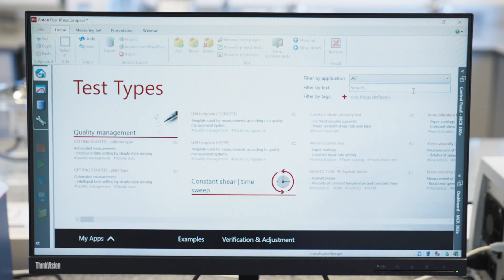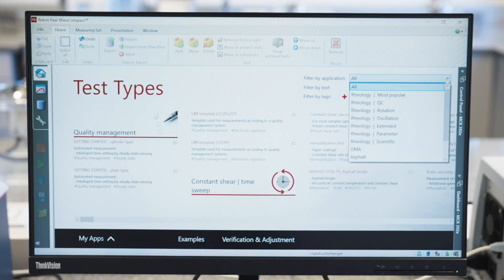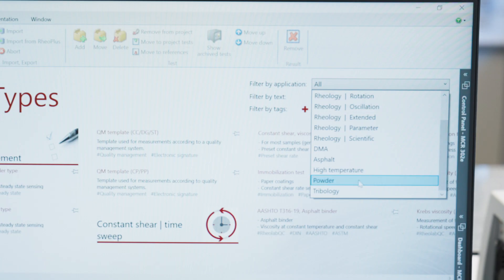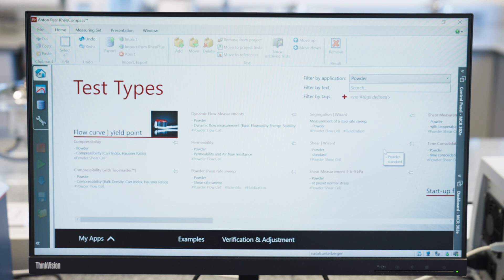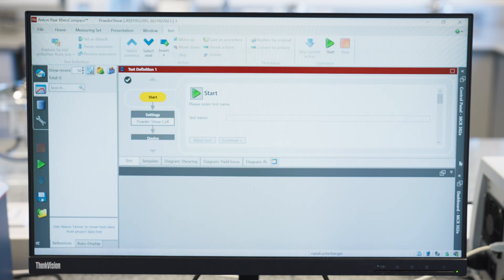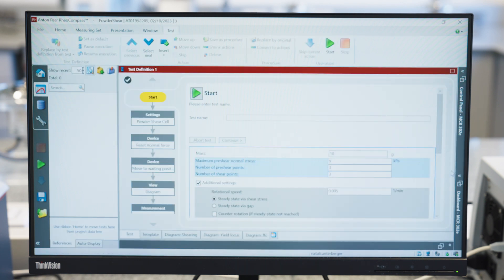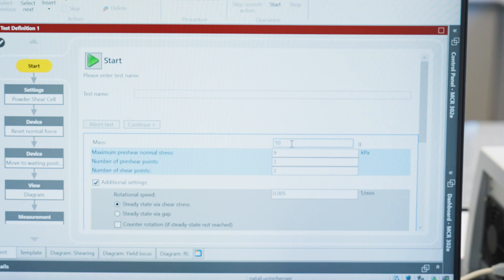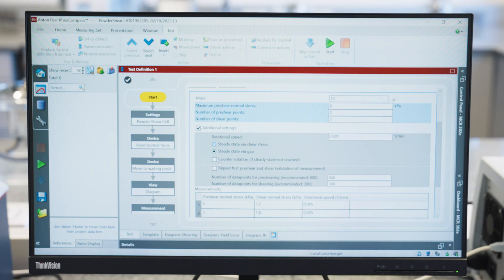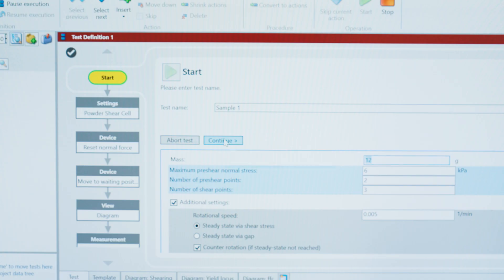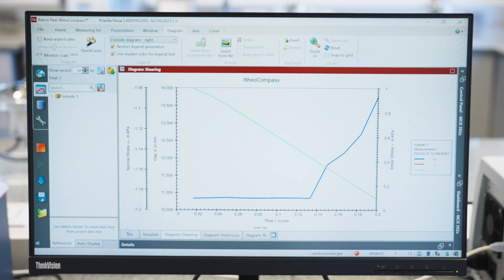In the software, set up the method using a wizard when possible. In the test types tab, select powder from the drop-down menu, then open the shear wizard to set up the analysis method. Here, enter the mass value because it will be needed to calculate the bulk density at each compression step. Additional settings can also be adjusted based on the characteristics of the powder being investigated. A table with all set parameters is then generated. Now the analysis can start.